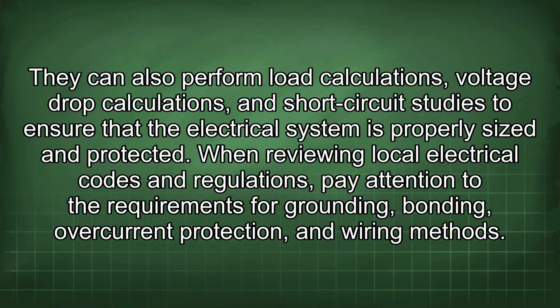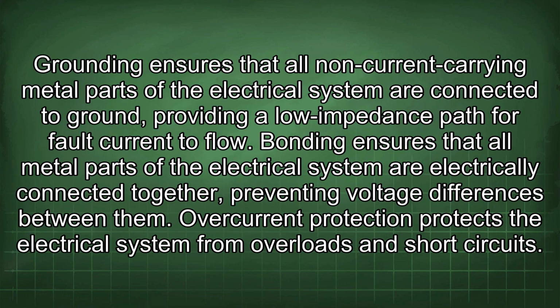sized and protected. When reviewing local electrical codes and regulations, pay attention to the requirements for grounding, bonding, overcurrent protection, and wiring methods. Grounding ensures that all non-current carrying metal parts of the electrical system are connected to ground, providing a low impedance path for fault current to flow.